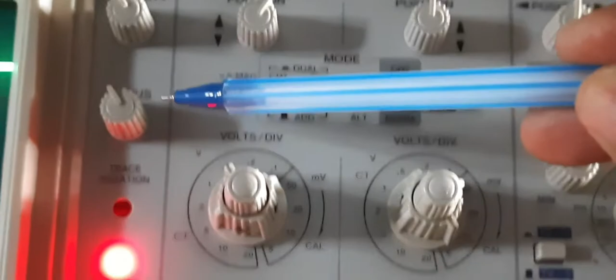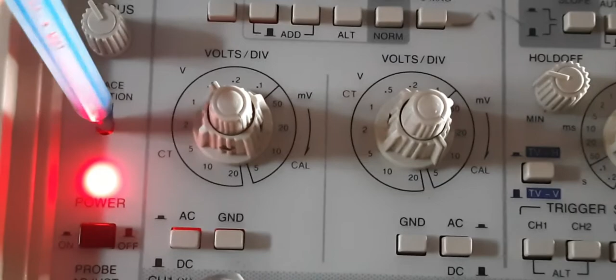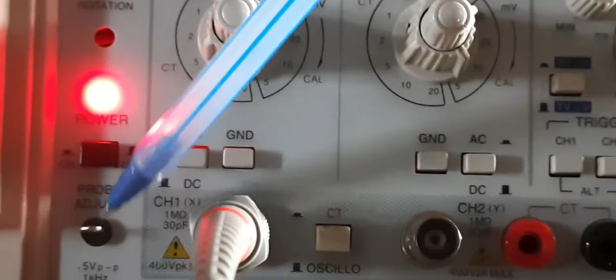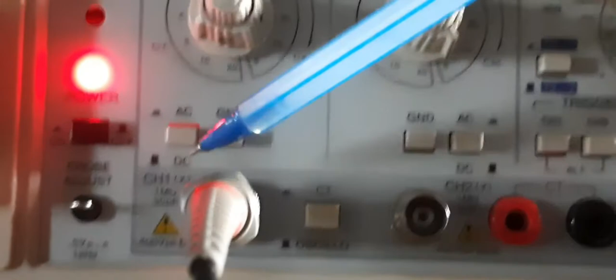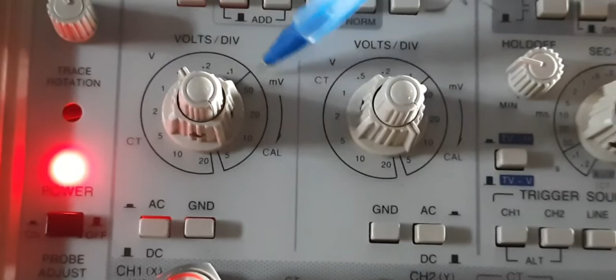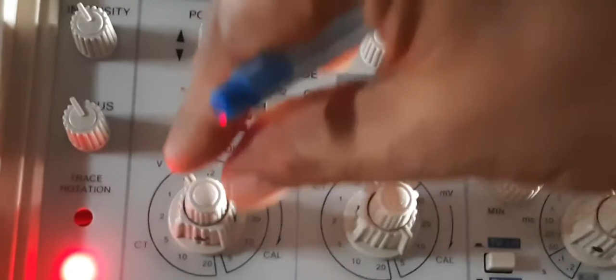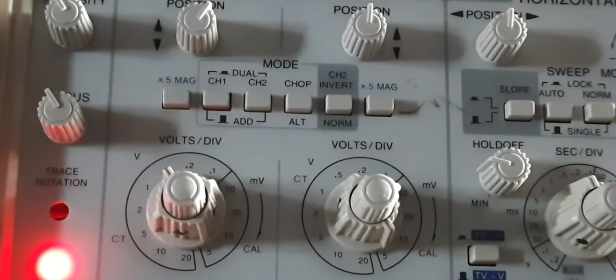Once again, a revision: intensity knob, focus knob, trace rotation, which you can adjust using a screwdriver over here, power, calibration point, first channel, ground, AC/DC point, volt per division for this first channel. Here it is volt, here it is millivolt. This right position is calibration. See to it that it is always in the calibration position. This is channel 1. If you are doing only channel 1, select channel 1. If you are using both the channels at the same time, select both the channels, then you will get 2 traces over here.